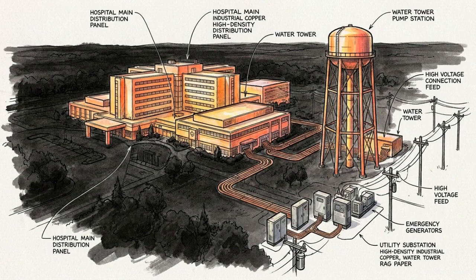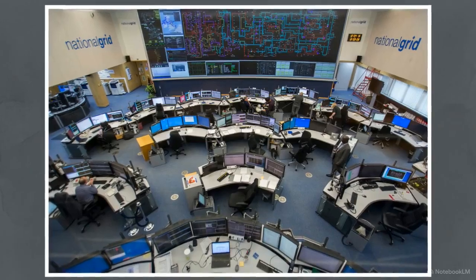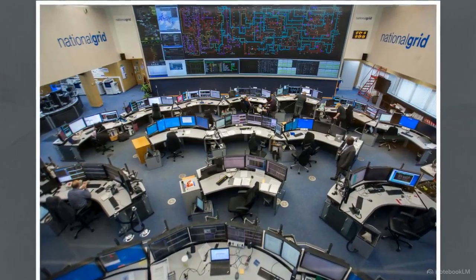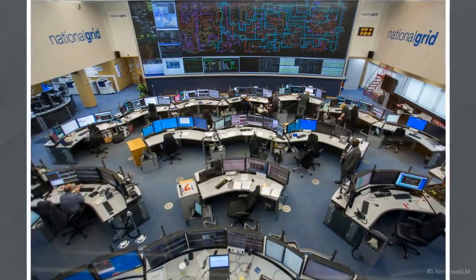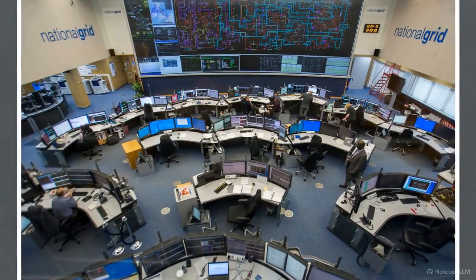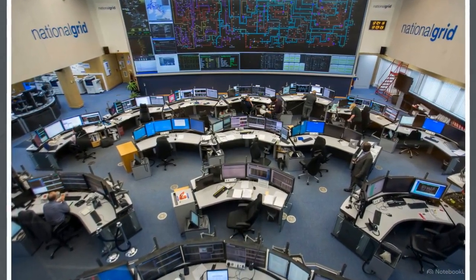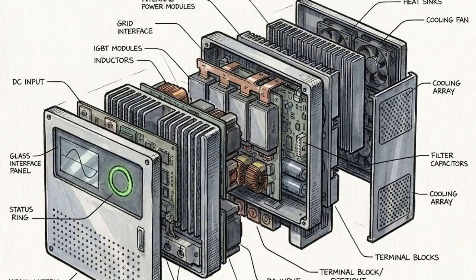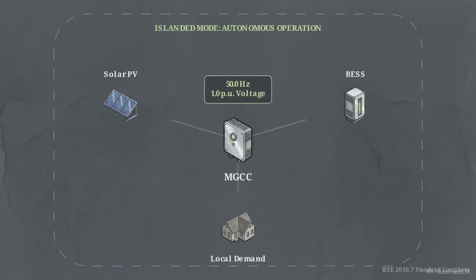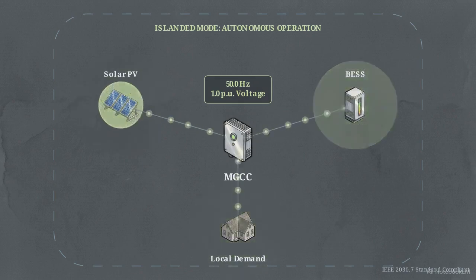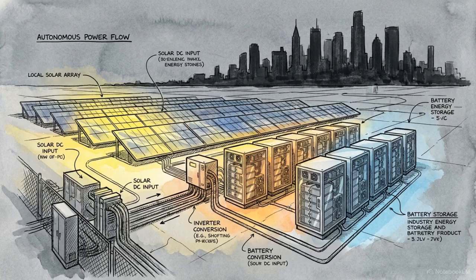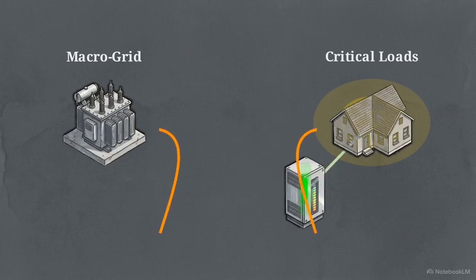Traditional distribution is centralized. A control room dictates commands to a passive network. When external communication lines are cut, the local system loses instructions. But a modern microgrid is engineered differently. It is a highly calibrated autonomous control system built for survival. To achieve resilience, local infrastructure must function as its own independent authority the exact second the external connection fails.